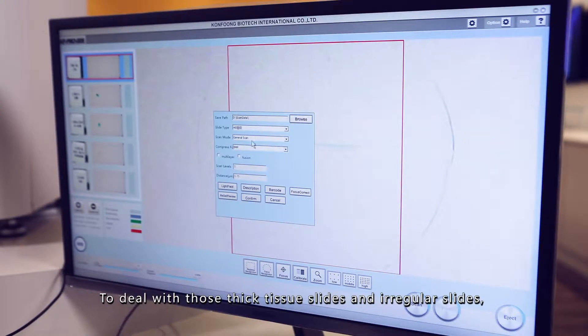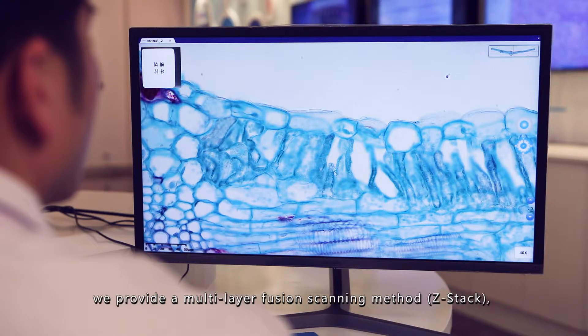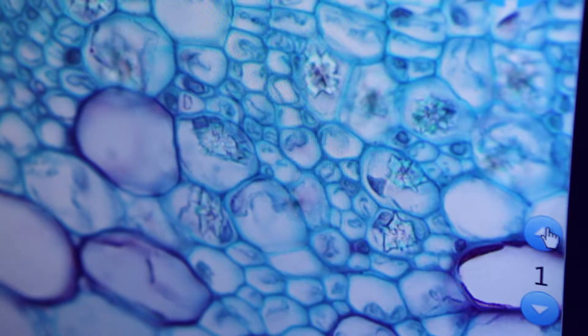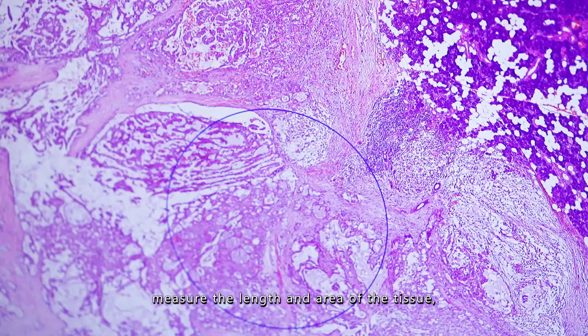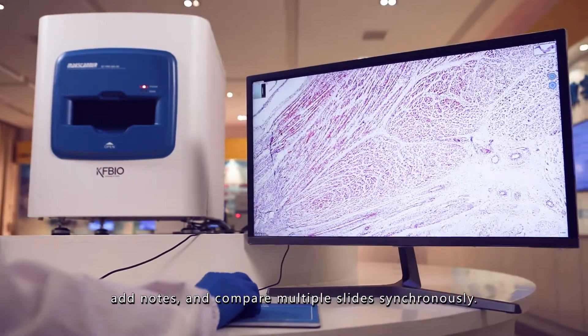To deal with thick tissue slides and irregular slides, we provide a multi-layer fusion scanning method, Z-Stack, so that different types of slides can be clearly scanned. After scanning, a digital whole slide image will be outputted. Pathologists are able to browse quickly, measure the length and area of tissue, add notes, and compare multiple slides synchronously.